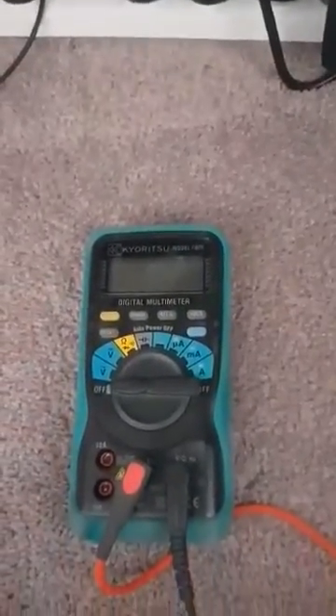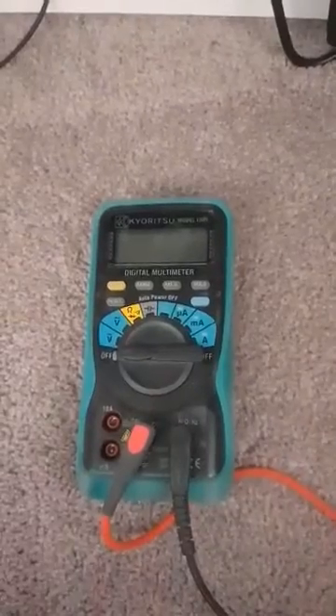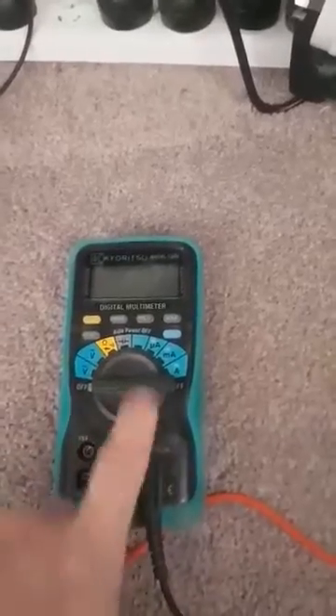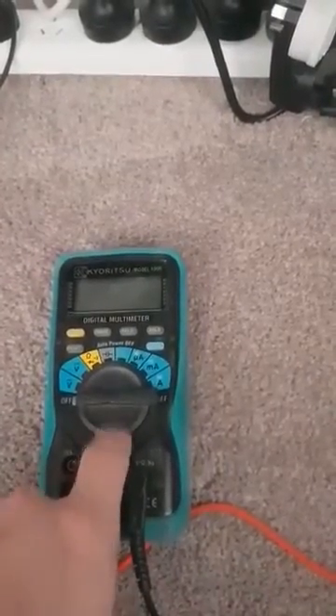The things you're going to need is a multimeter. I don't recommend a volt stick — the ones that you touch the power point and it lights up. Sometimes it just won't light up and give you a false indication that it is de-energised when it actually isn't. So before using this meter, you're better off going around and testing it on a few different power points just to make sure the meter is working correctly.